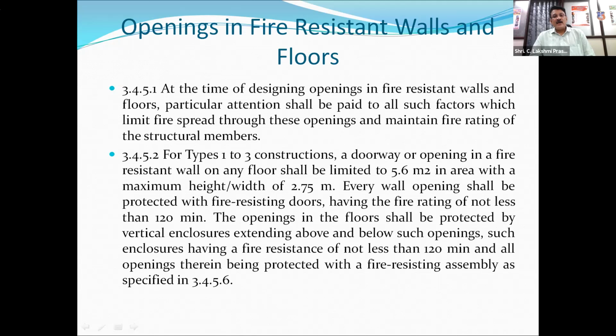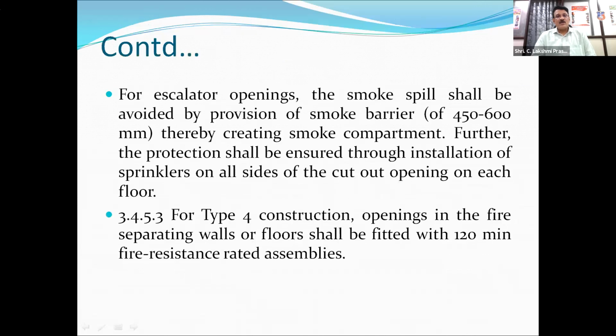Then they have prescribed the doorways, how much opening should be given in the floors for a doorway. It is 5.6 square meters in area with a maximum height of 2.75 meters. Fire resistant doors have to be provided with a minimum 2 hour fire resistance. The opening in the floor shall be protected by vertical enclosures extending above and below such openings. Such enclosures shall have fire resistance of not less than 120 minutes, and all openings therein shall be protected with a fire resisting assembly as specified in 3.4.5.6, that is the clause number.